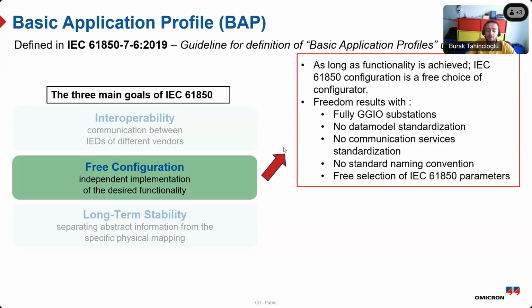We have seen a lot of 61850 substations where this free configuration allowed us to freely define the data model, the signal flow, the communication services, without any standard naming convention. Maybe this resulted in some substations with fully GGIO utilized, and no logical node usage. The semantics are lost, and then we convert 61850 into a data point protocol like 104 or Modbus. That was not the case we wanted to achieve with 61850.